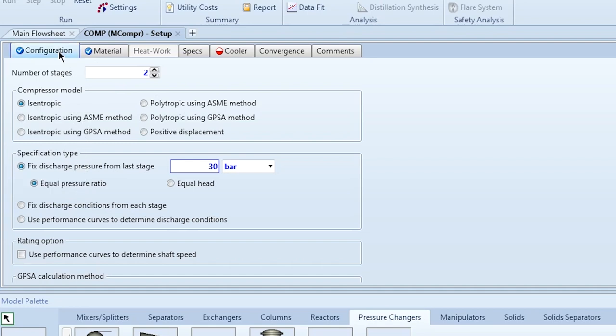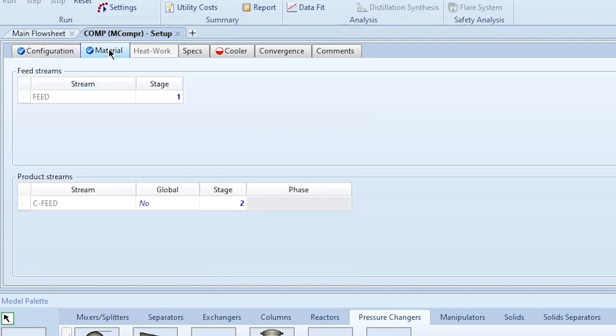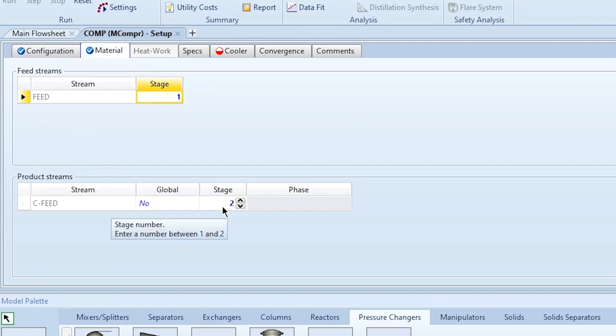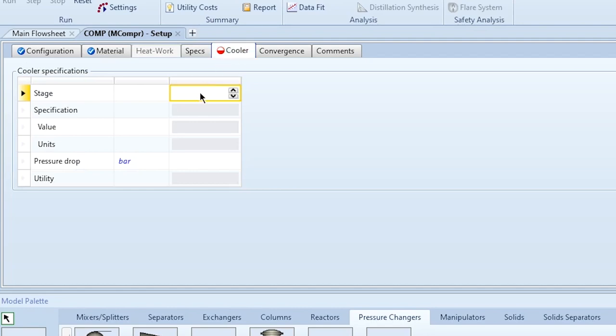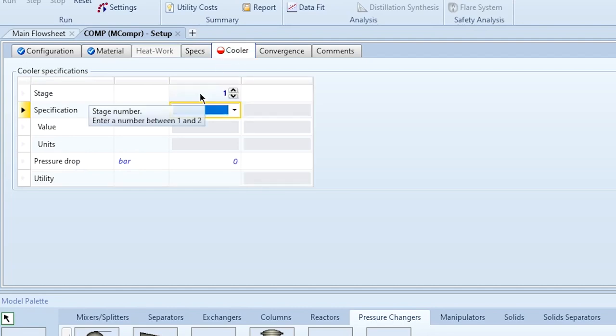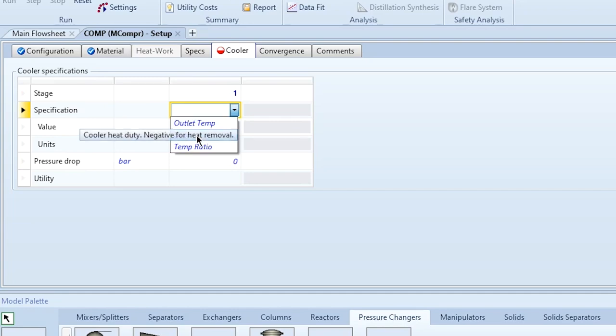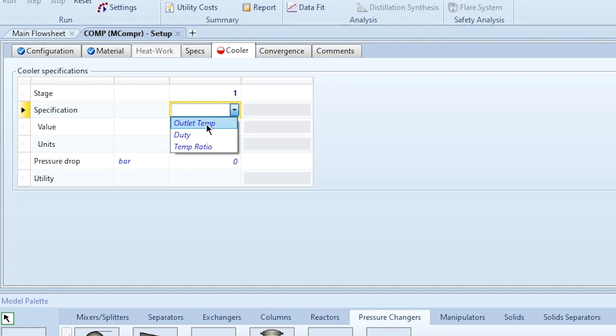After specifying the number of stages, compressor model, and specification type, the Configuration tab is complete. In the Materials tab, the feed enters at stage one and the product exits from stage two — this is already set. In the Cooler tab, you specify the intercooler, which is installed after stage one — not the after-cooler at the outlet of the last compressor.